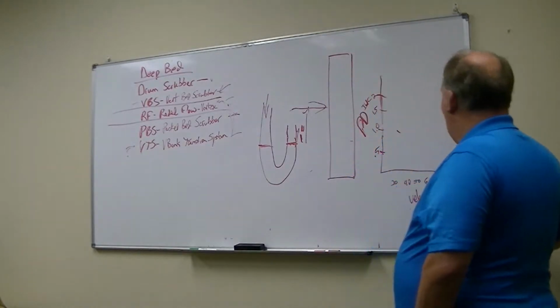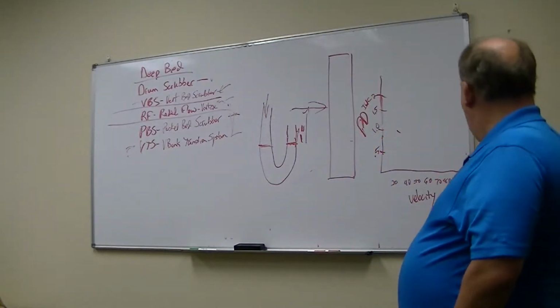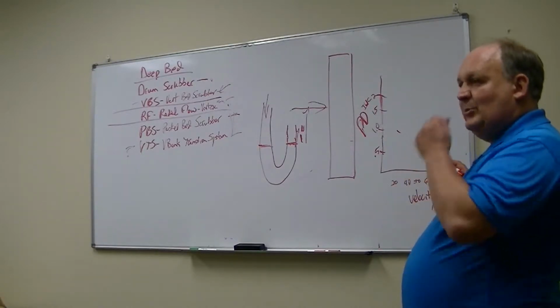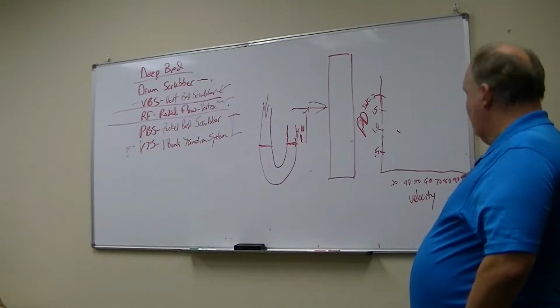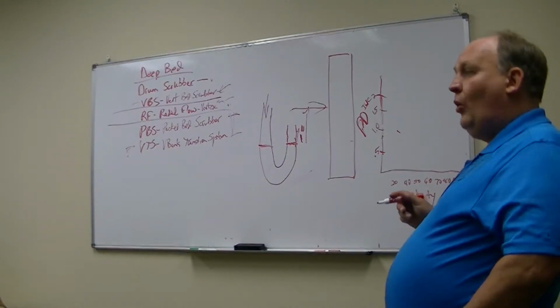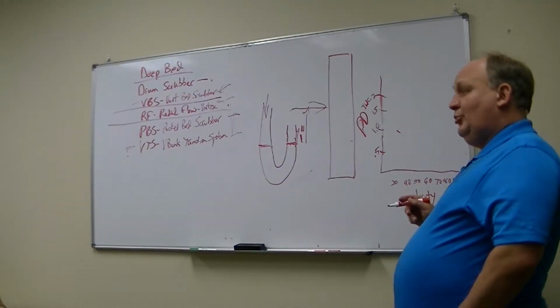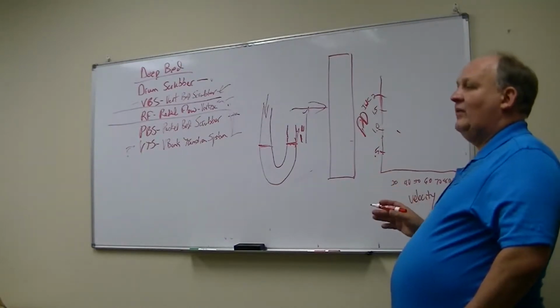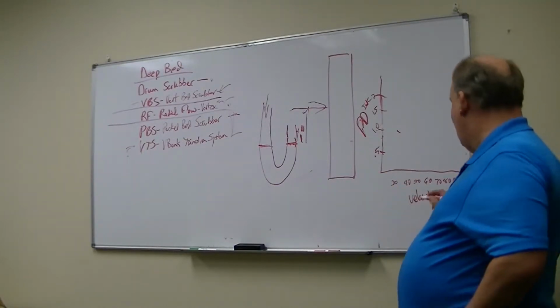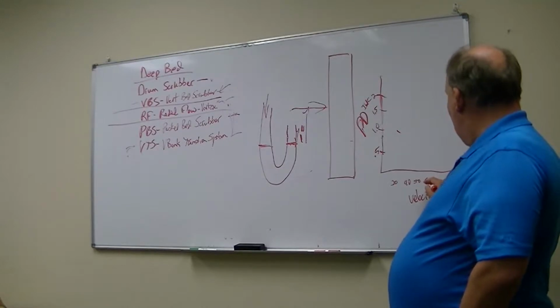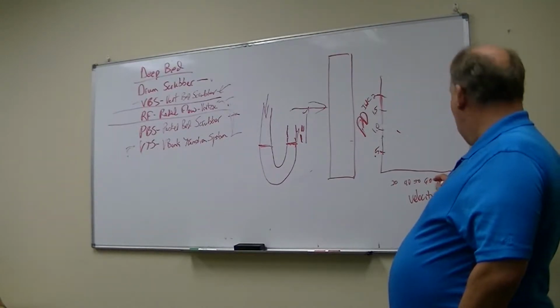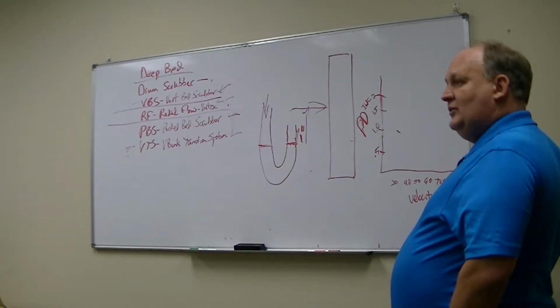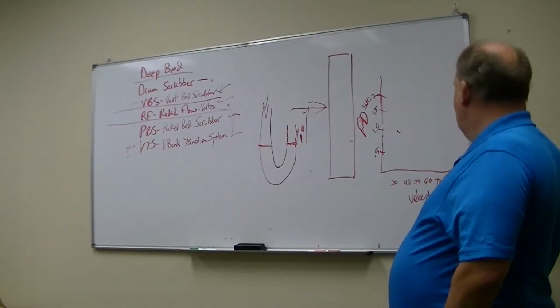Okay, so I've mentioned to you the maximum airflow that we push air through is about 100 feet per minute. The reason that we don't do more than 100 feet per minute is because the pressure drop gets kind of crazy after that. It gets super high because it's exponential. So the amount of pressure change from 60 to 70 is far less than the amount of pressure change from 90 to 100. Okay, all right.